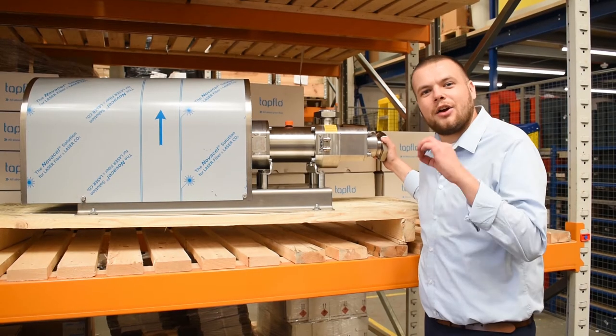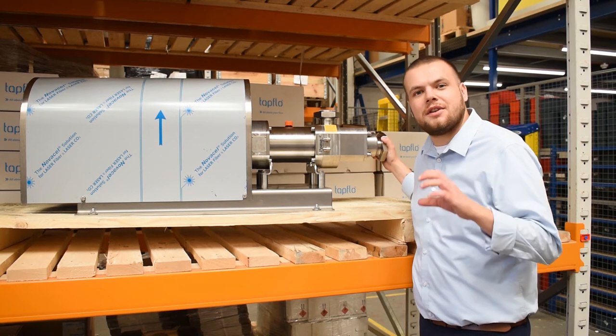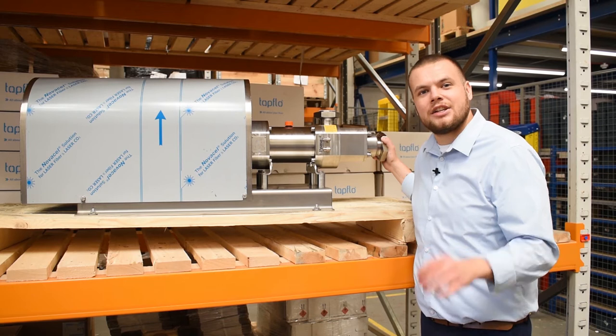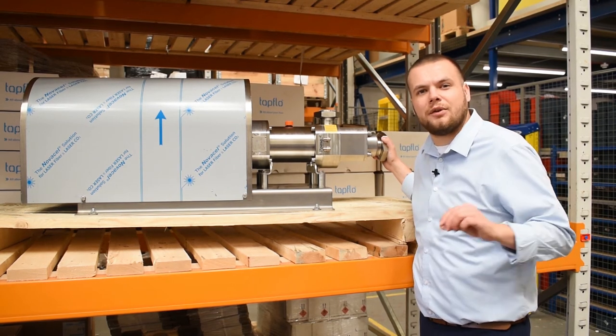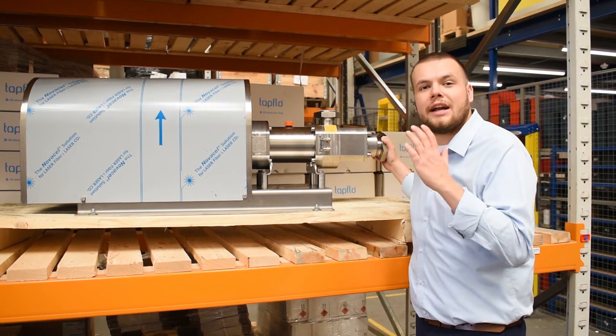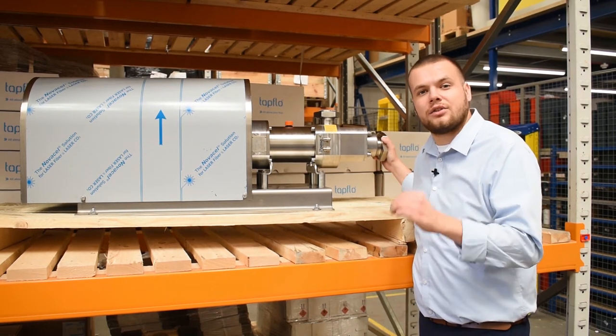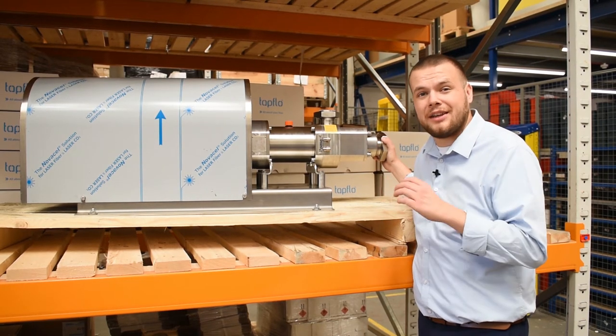Now we're going to go through the benefits of a twin screw pump. Due to the versatility of the twin screw pump, there are many benefits — we'll leave a link below that covers them all, but in this video we'll just go through a few. To start off, we'll talk about flow rate. The twin screw pump can reach really high flow rates and can achieve those flow rates at really high viscosities — it can actually go up to a million centipoise, which is pretty thick.